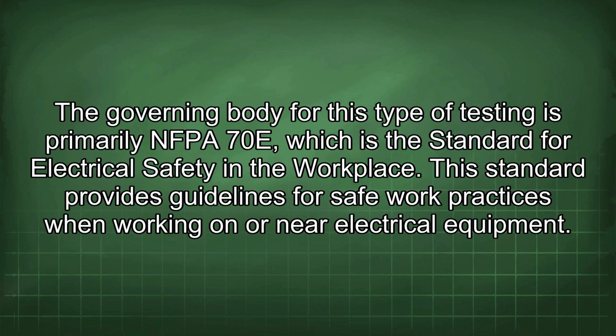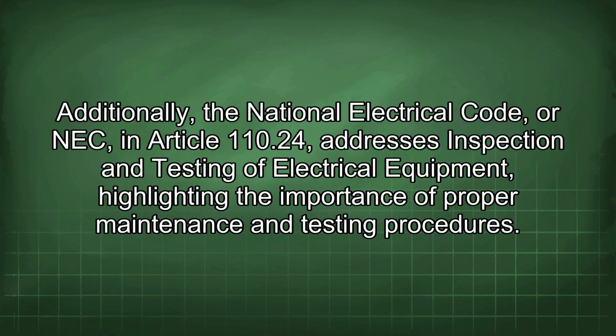The governing body for this type of testing is primarily NFPA 70E, which is the standard for electrical safety in the workplace. This standard provides guidelines for safe work practices when working on or near electrical equipment. Additionally, the National Electrical Code, or NEC, in Article 110.24, addresses inspection and testing of electrical equipment, highlighting the importance of proper maintenance and testing procedures.